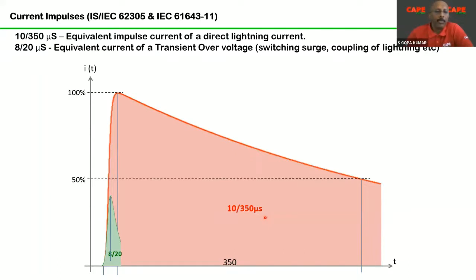Now, the two subjects you should understand are components of external lightning protection. Say you have a building, with some clamps, clips, conductors. Those need to be tested with the 10 by 350 microseconds wave shape. The smaller devices such as SPDs are sometimes tested with 10 by 350 microseconds, which is called a type 1 SPD. Sometimes the SPDs are tested with 8 by 20 microseconds, which is called a type 2 SPD.